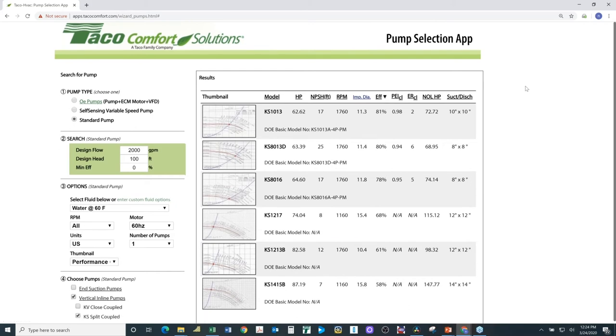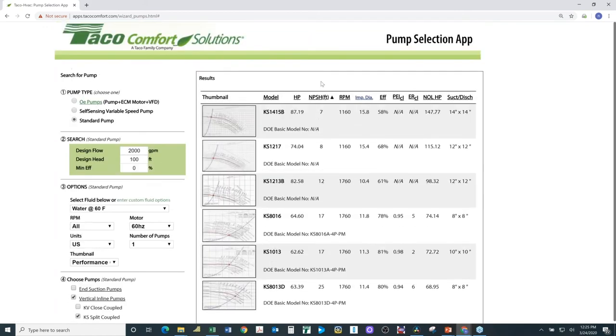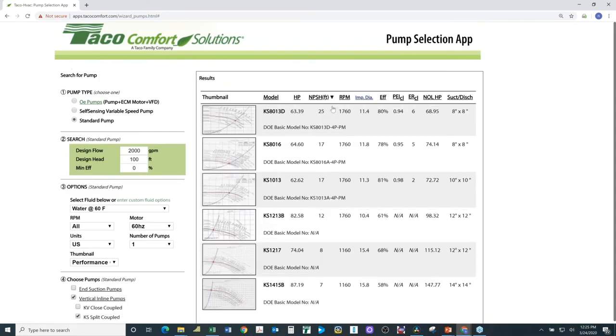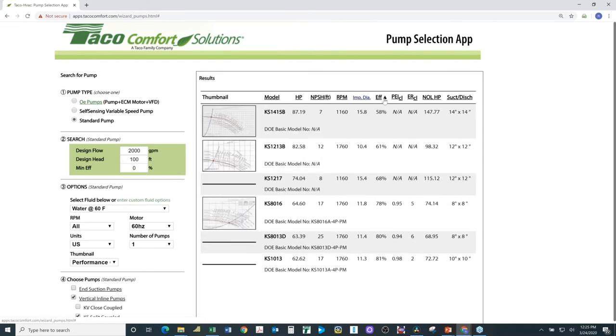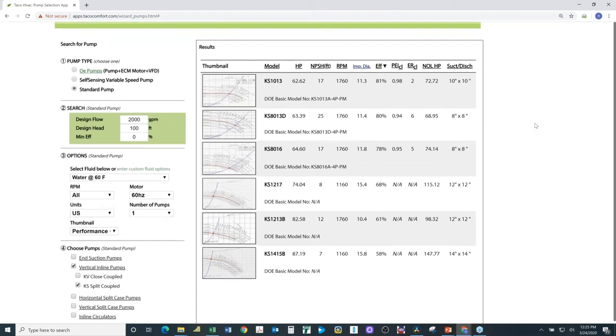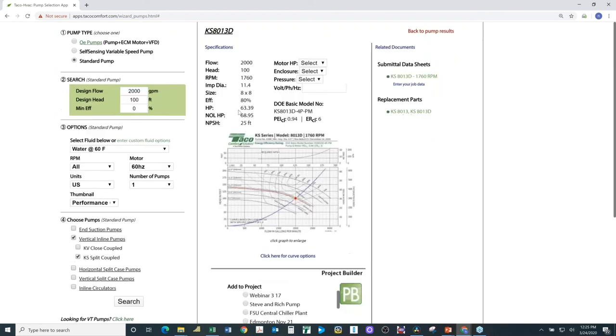You'll notice it also shows the NPSH value. Clicking on NPSH sorts it from lowest to highest, or highest to lowest. I'm going to leave it sorted by efficiency, highest to lowest. I'll select the second pump — a KS8013D at 80% efficiency. Scrolling down, the motor horsepower or brake horsepower is 63.39 and the non-overloading horsepower is 68.95. I'll talk about non-overloading horsepower in a moment.